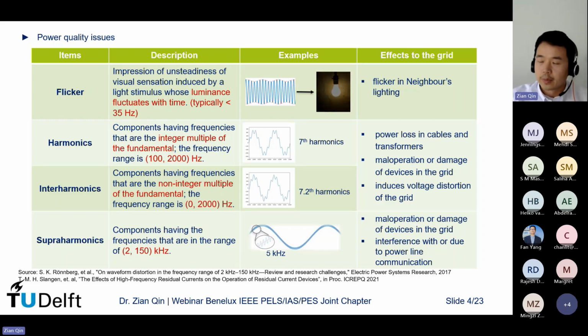However, this 30 milliampere is actually only at the fundamental frequency. If there are high frequency components in the leakage current, then according to some testing reports, the higher the frequency, the higher the magnitude of current that is needed to get this RCD device tripped, which makes the safety level low, right? So people are already noticing this phenomenon, and they are looking into it and trying to solve it.